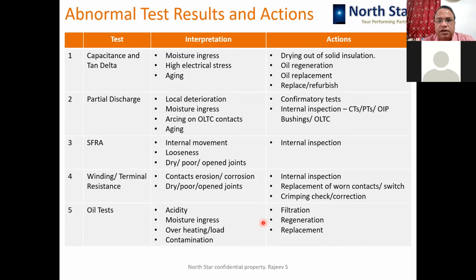And as we said earlier, solid insulation irreversibly gets aged. So that threshold should always be watched. It shouldn't get so much moisture that beyond that we cannot do anything, and the transformer life gets reduced because of the delay in drying out the solid insulation.